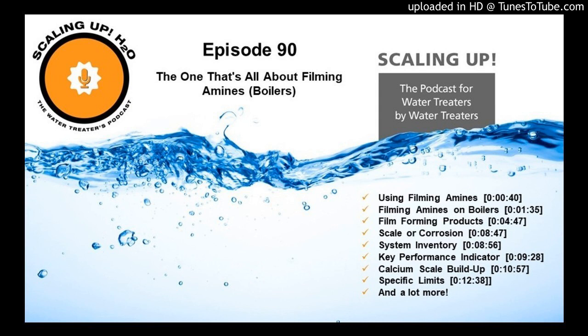I can tell you the first time I used a filming amine product, it was several years ago. We didn't have a lot of information out about it. Somebody asked me to try this. It was a brand new system, but there was a lot of flash rusting that went on inside it. So we put the product in at the maximum level because that's what we were told to do. And I really thought we just purchased that customer's boiler.